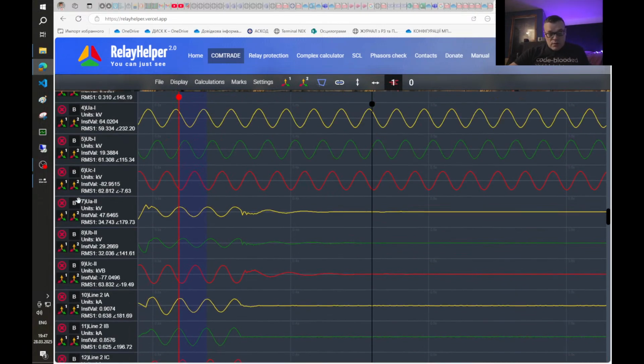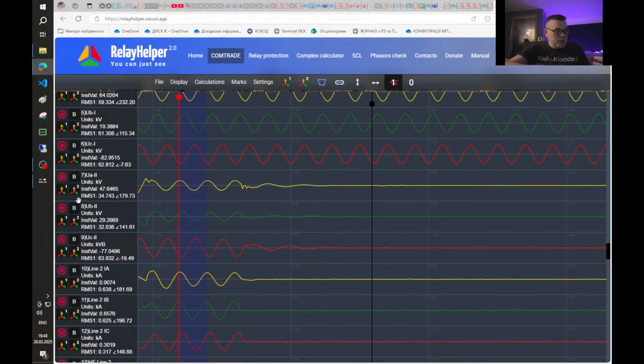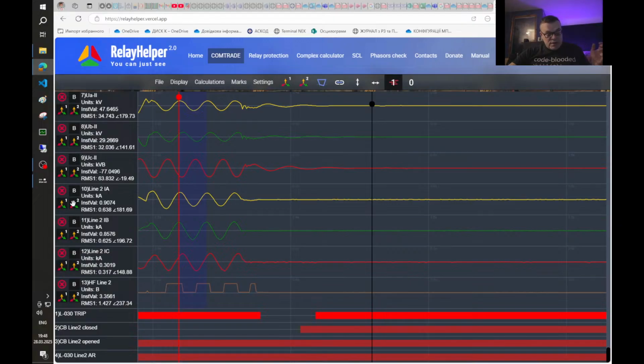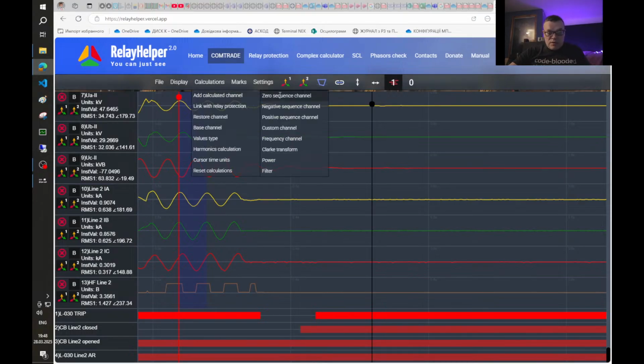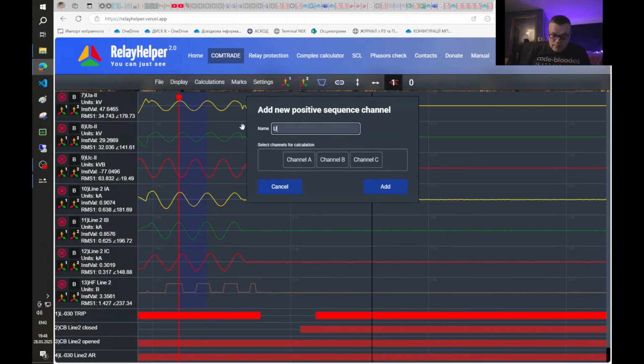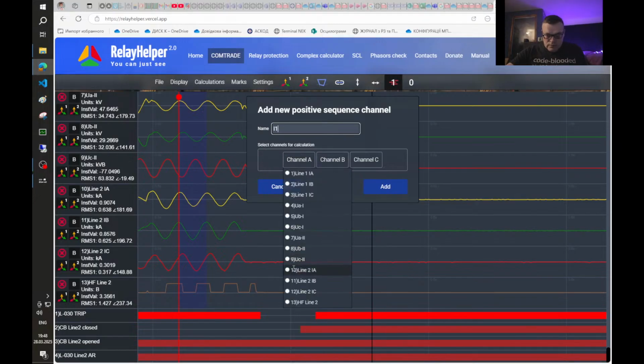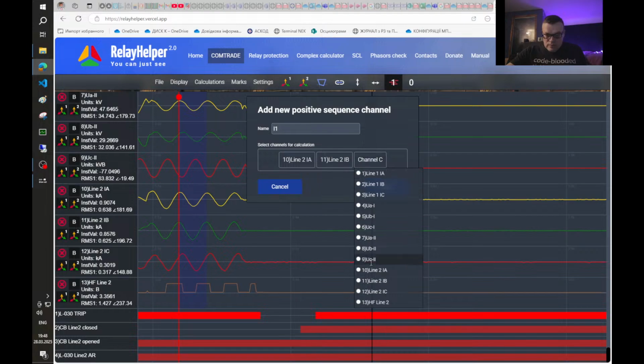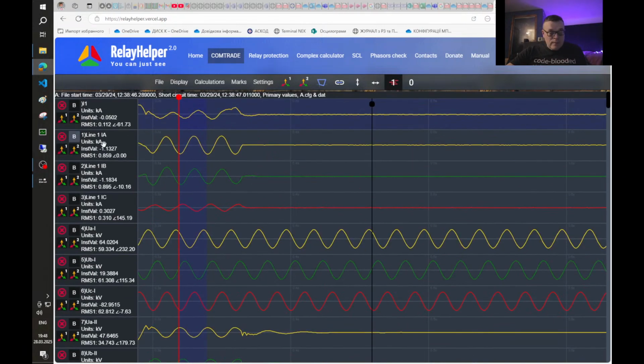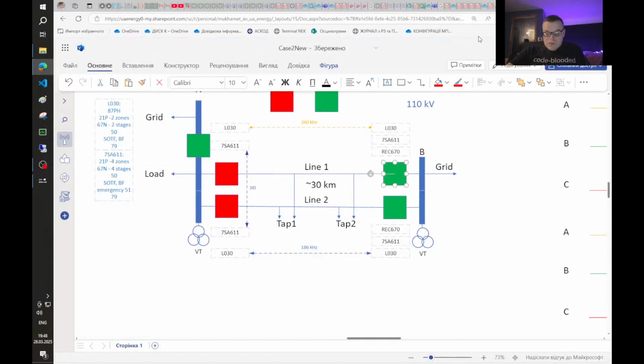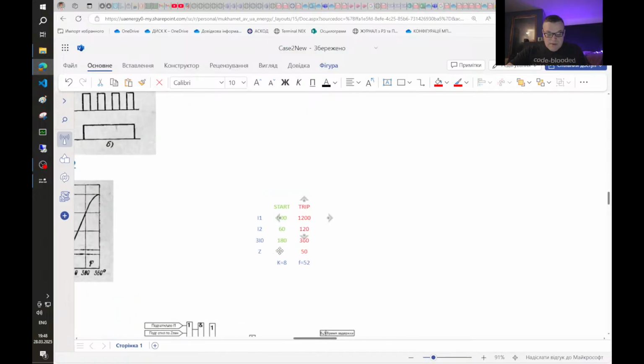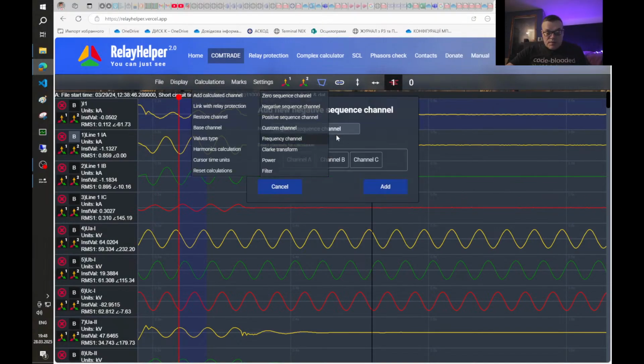The process will be pretty much the same. First we will calculate positive sequence current, negative sequence current, and also zero sequence current. Let's start with positive sequence current. It's a little bit more than 100 amperes. So let's return to our settings. It was not enough to initiate not only trip but also start. Let's return and calculate negative sequence current.